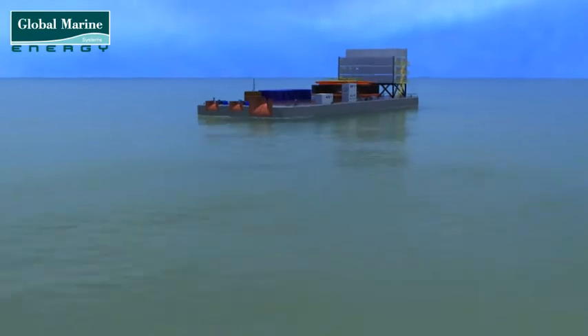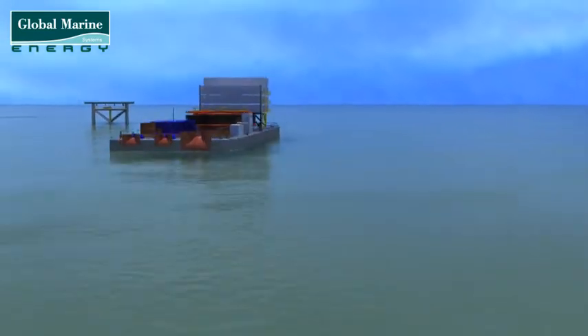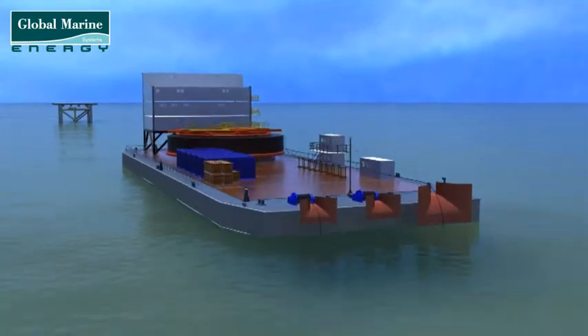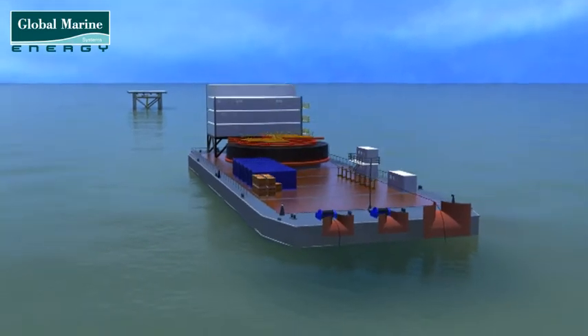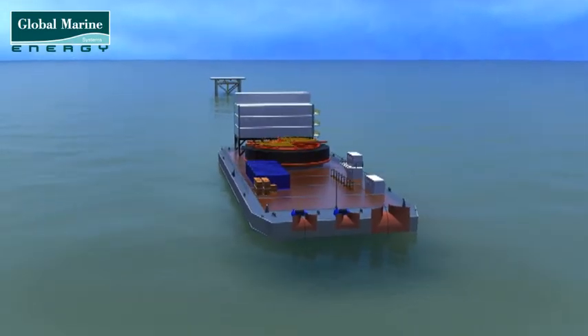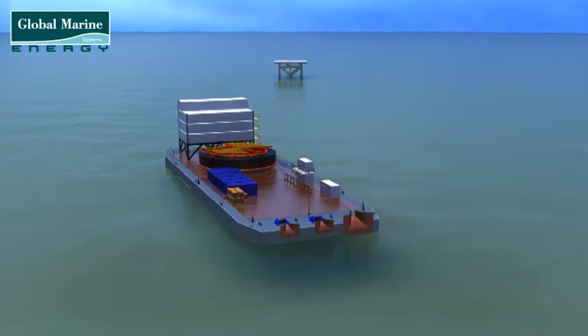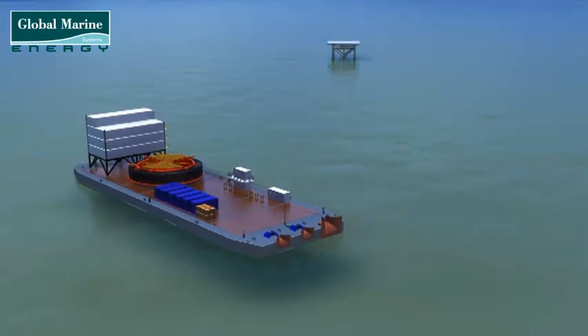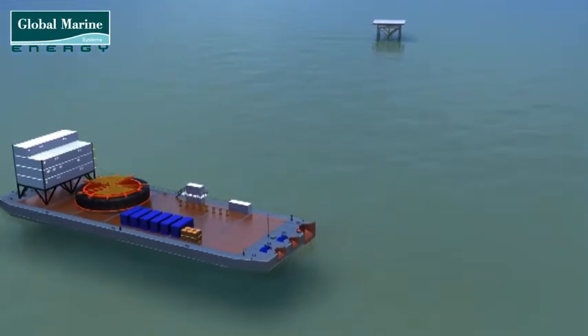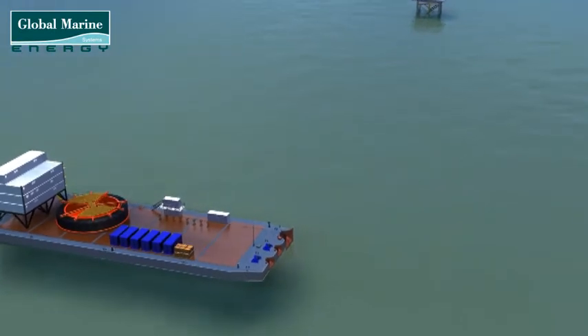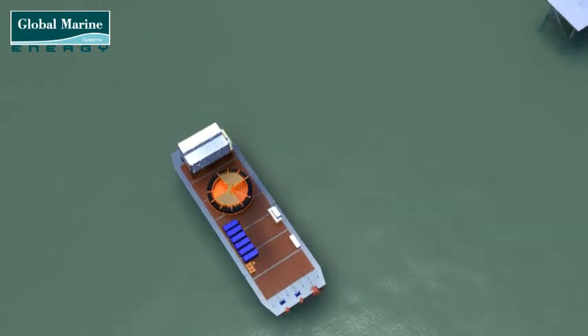The excess cable is coiled back onto the cable carousel as the barge reverses back along the route. Back at the starting point, the barge is manoeuvred ready for the J-tube operation, with the chute closest to the substation. Having adjusted the barge correctly, the excess cable is laid on the seabed in an S-bend movement until the point at which the messenger line can be recovered from the J-tube.